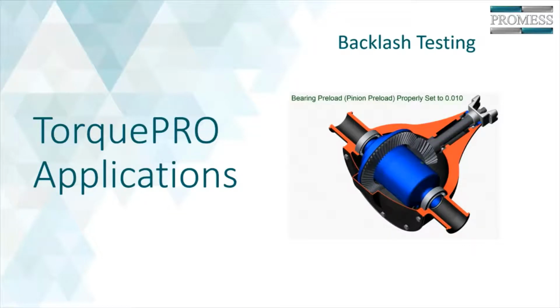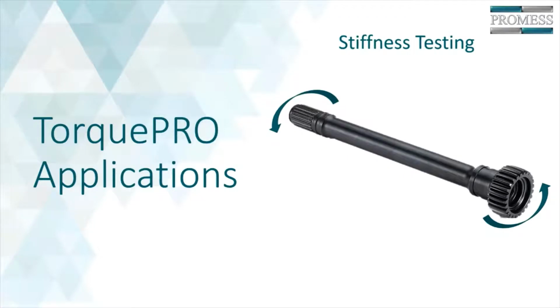Spline backlash testing is very similar to a gear drive. However, in most cases, it is done using a single point backlash test. Very similar to backlash testing is stiffness testing. It's very closely related to single point or static backlash testing. One end of the shaft or component is held fixed while the other has a specified torque applied to it in both directions. The positional difference between the positive and negative torque values can be used to determine stiffness.